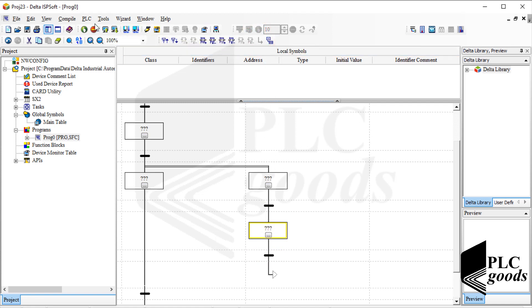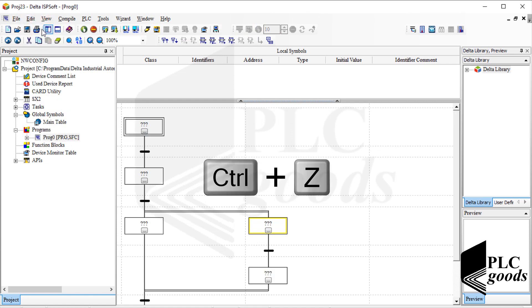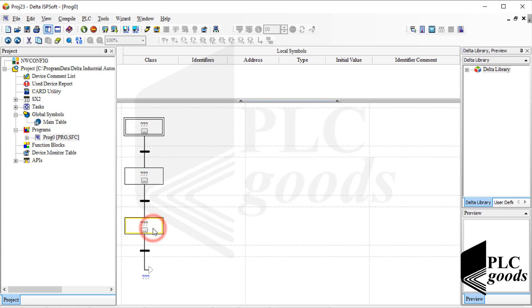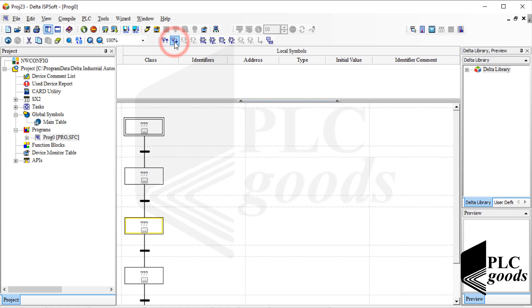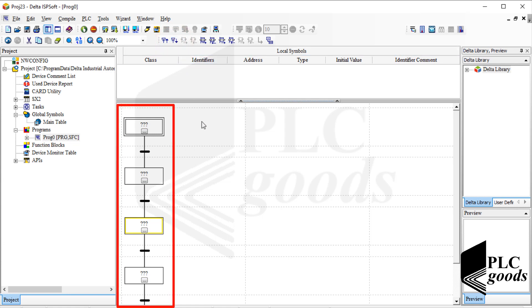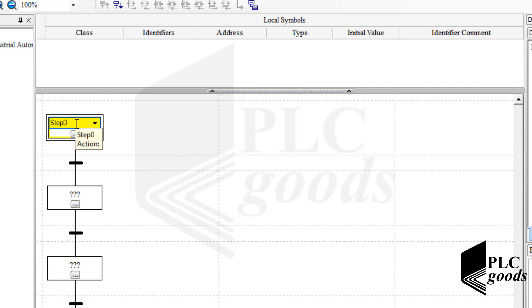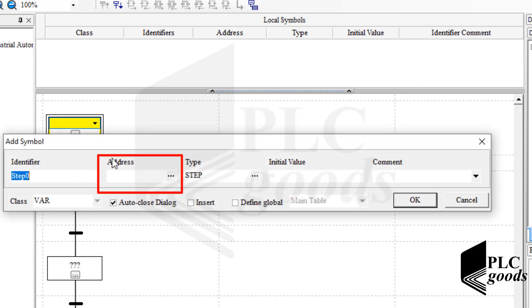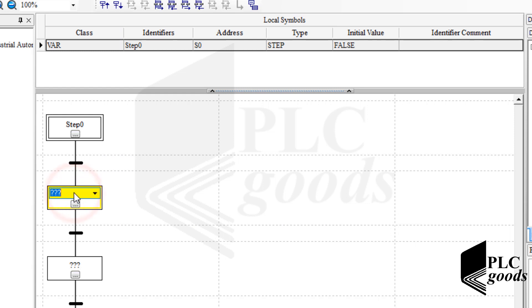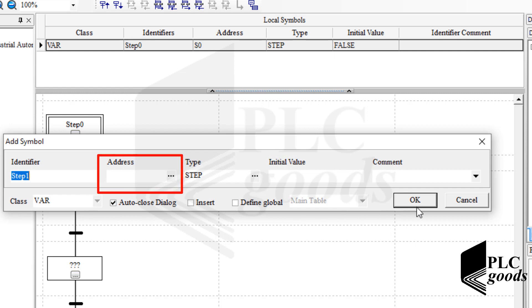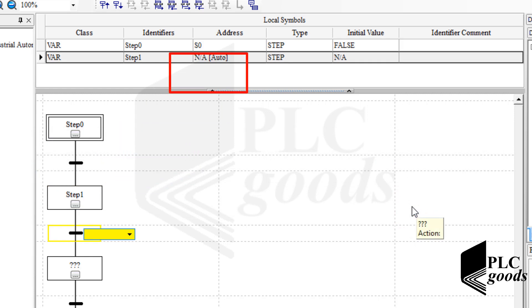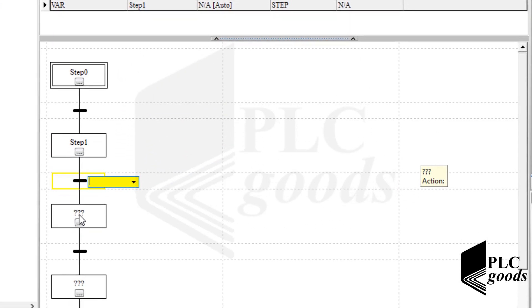For the first program, let's create a simple sequential chart with four steps. Let's specify the address or name for each step. Try to use a meaningful symbol for each step and then assign an address in the local symbol table. Each step address must start with the letter S and then a number, like S0, S1, or S10. If no address is specified, the PLC will automatically select one when you compile.